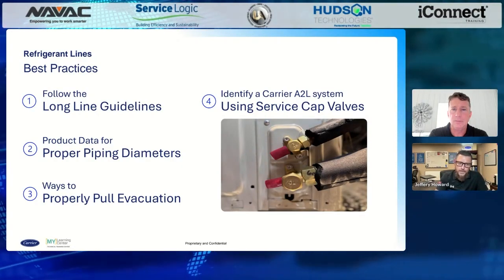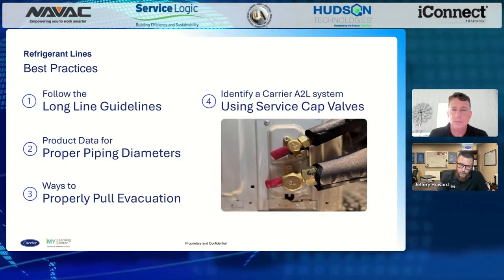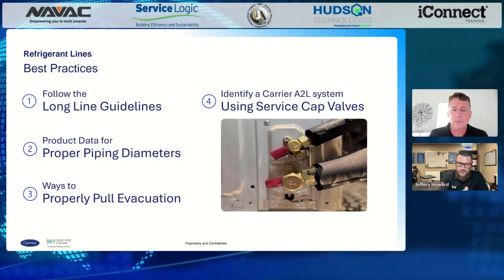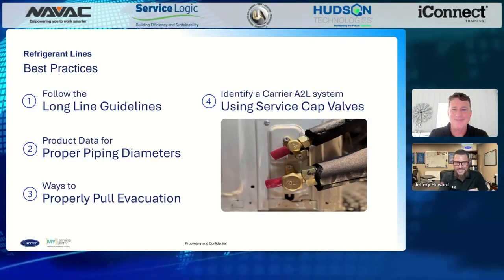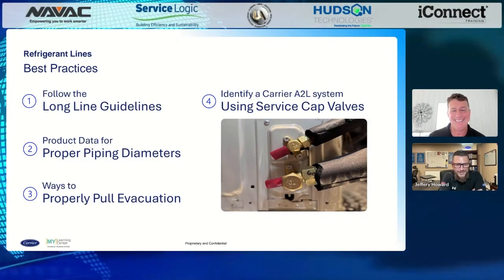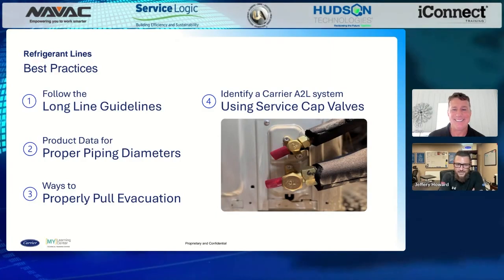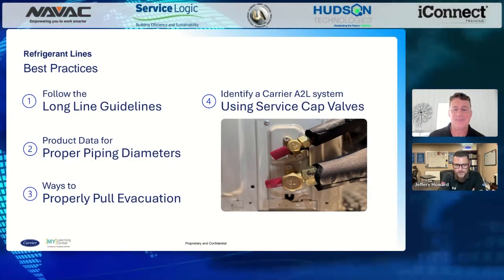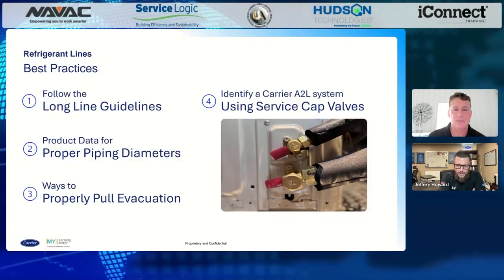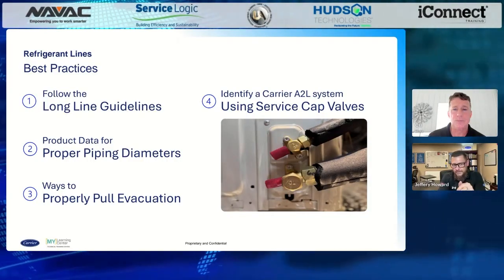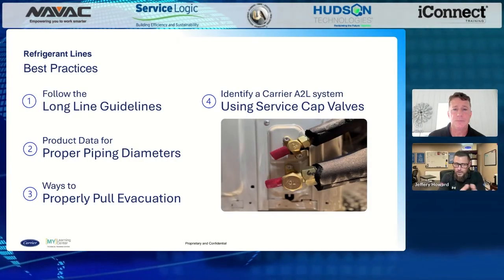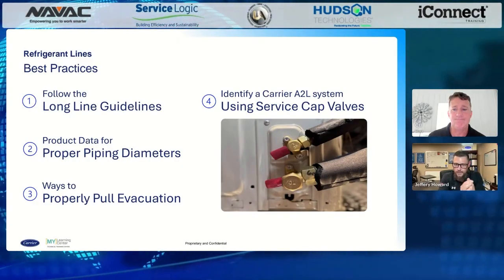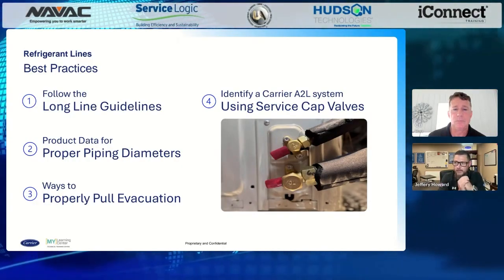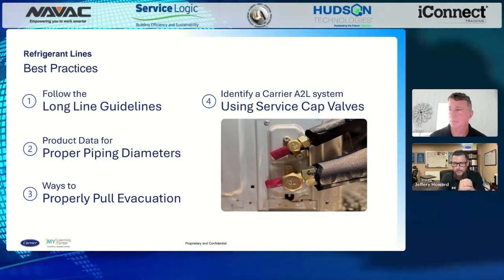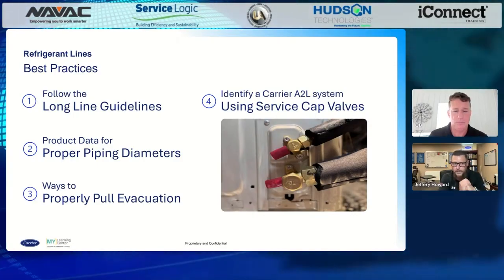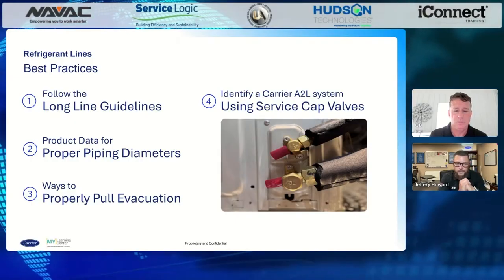You don't always have to make it the size of the actual service valve. We used to say bells, but now with press fittings, you're going to have some different things there with our straight stub outs. But it does not have to necessarily be that size. It depends on the application that we're installing. So on piping diameters, I always love to tell people, look at the product data, the long line guidelines, as you mentioned earlier and pulled up. And also, like I said, our residential air conditioner and heat pump application guideline using the Puron refrigerant, along with the service manual, is very, very beneficial out there.